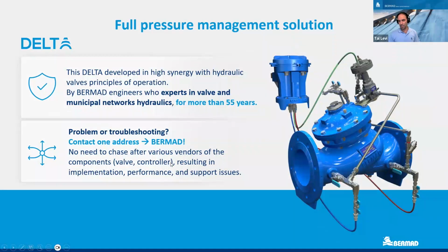And the second point is regarding what the client is looking for. In the end, the water utility engineer, all he cares about is that the downstream pressure will be based on the desired set points that he specified. And if he doesn't get the desired pressure, he gives a phone call to the valve manufacturer. The valve manufacturer checks the valve, says everything is fine, and then it goes to the controller company, and the controller company says the same, and he stays without an answer. So the fact that here we have one responsibility for the entire system, and we will make it work, that's critical.